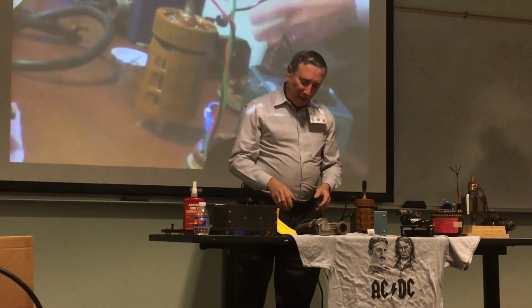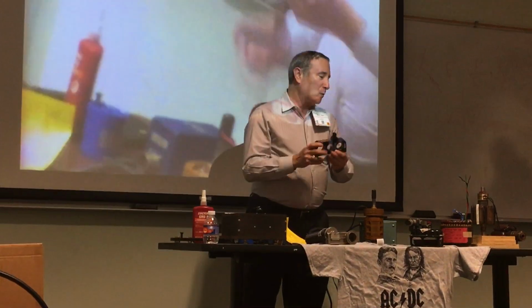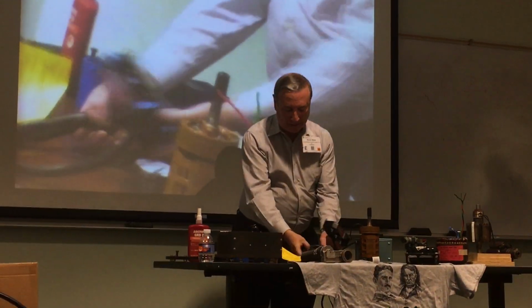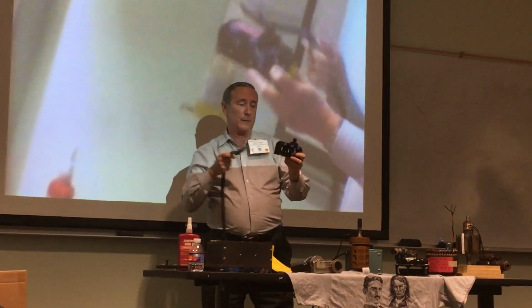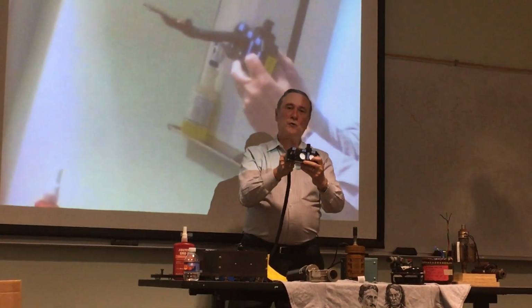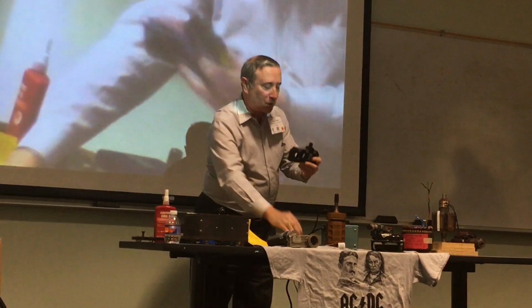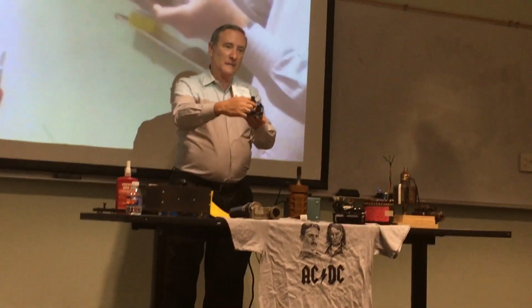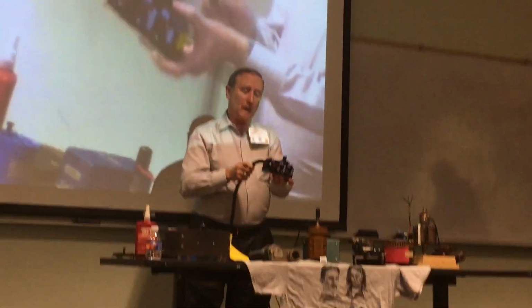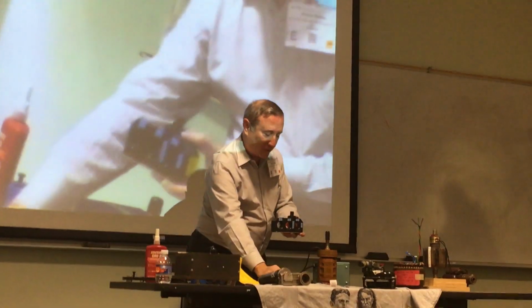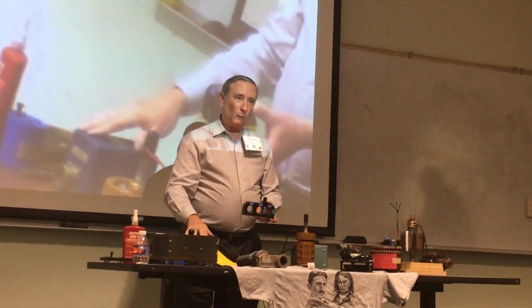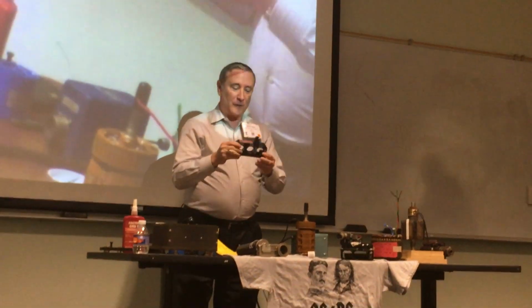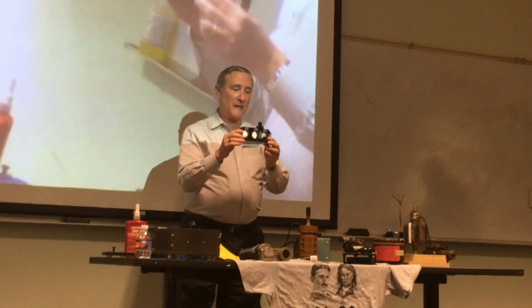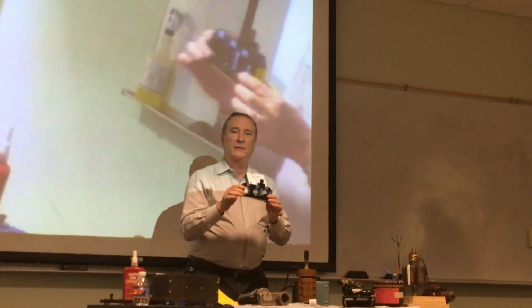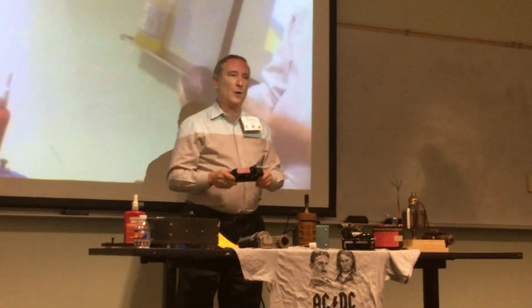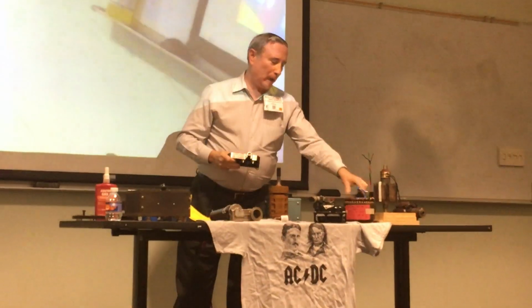One of the other safety factors on an airplane is a current transformer. The 3 wires coming out of the generator, each one a typical feeder cable, go through this current transformer to the distribution box on the airplane. And inside this current transformer are 3 separate coils of wire. If any feeder cable is overloaded or shorts to ground, it sends a pulse out its connector to the regulator, and the regulator will shut off the exciter voltage to the generator. Well, these are on the airplane, they're also in the power plants. If any phase is overloaded, this is what senses it. Anytime you travel on the road and you see the high voltage wires at the top of the pole, there's always 3 wires, because there's the 3 coils in the stator.